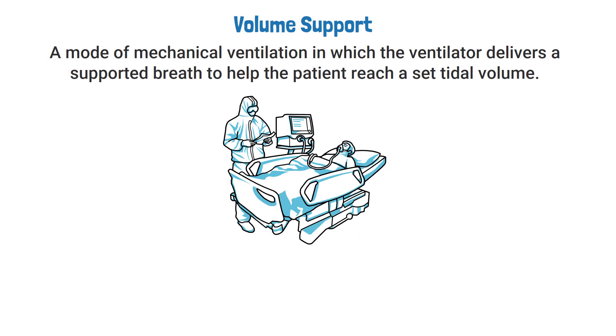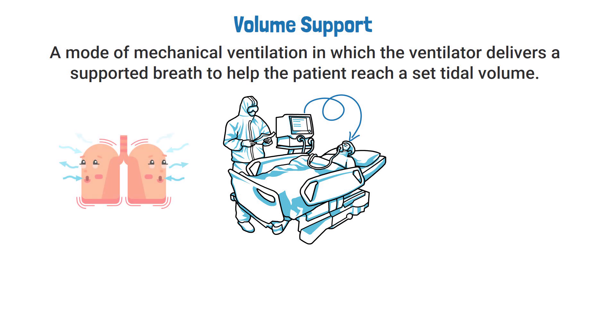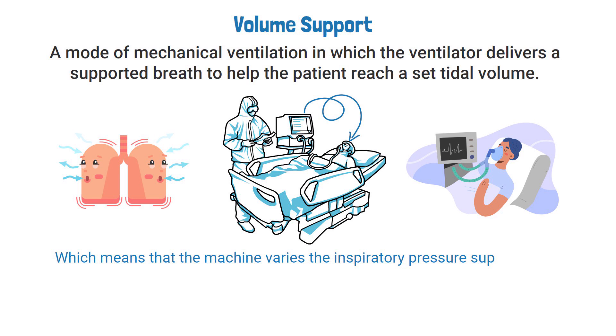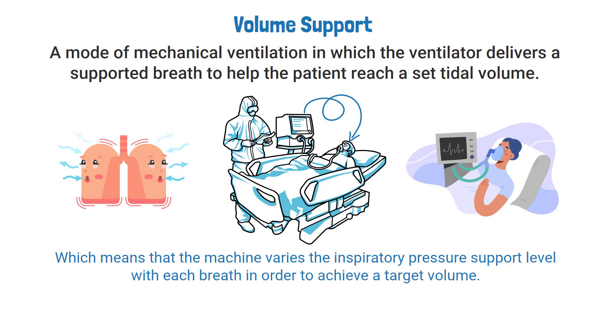Volume support is a mode of mechanical ventilation in which the ventilator delivers a supported breath to help the patient reach a set tidal volume. This mode is totally dependent on the patient's effort, which means the machine varies the inspiratory pressure support level with each breath in order to achieve a target volume.